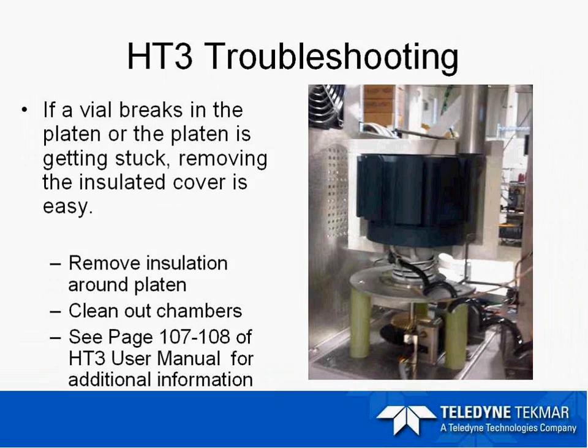If a vial should break inside the instrument, it is easy to get the vial out of the platen. Open the instrument and remove the insulation. There is also a worm gear at the bottom that you can turn to manually rotate the platen to get to positions not exposed. There is additional information in the user manual on pages 107 and 108 on how to do this.